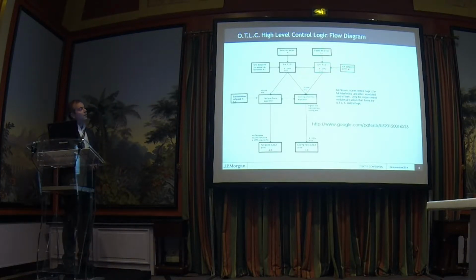Now, the idea with that is that you can now run your data center at whatever supply temperature you want, but the moment I turn the CRAC unit off in the middle, the 2 machines around it will instantly see a degree increase of air temperature. And then the two machines beside the one that's off, failed, or caught fire, or done whatever, it will then ramp up both machines around it and then supply. And if the valve gets to 100% cooling and you still haven't satisfied that return air temperature set point on the 2 side-by-side machines, then the fan will begin to ramp up.